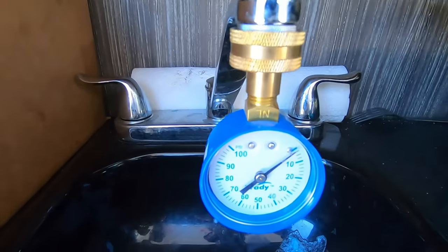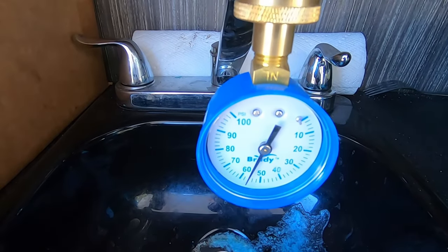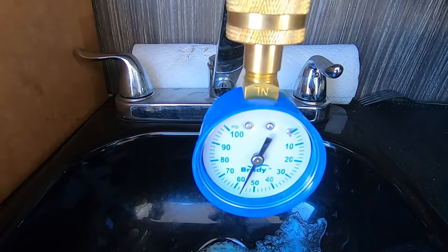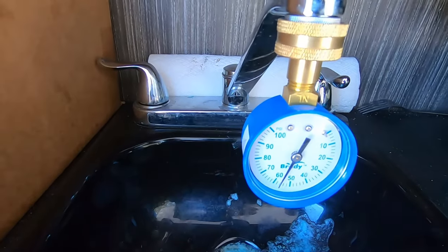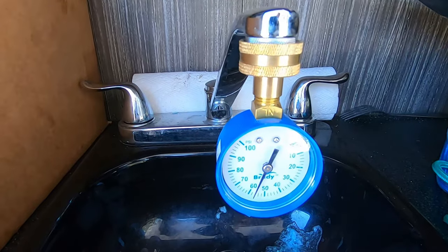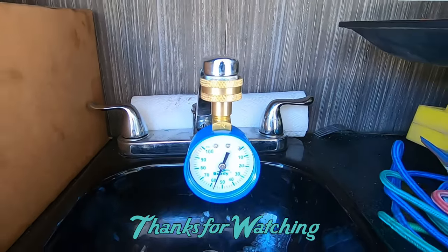The last test I wanted to do here was a pressure test, which I'm set to about 58 psi, which I'm okay with. So it's all good. I need to go release the pressure from the system now so I can get this off cleanly, and we are good to go. Thank you.